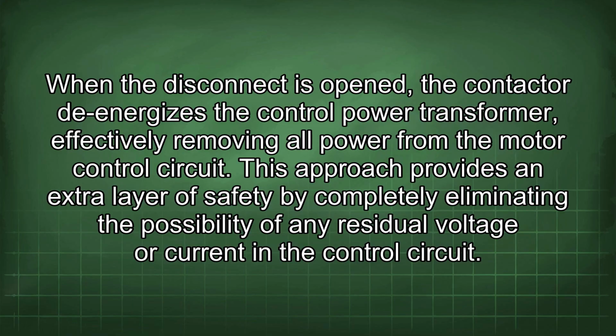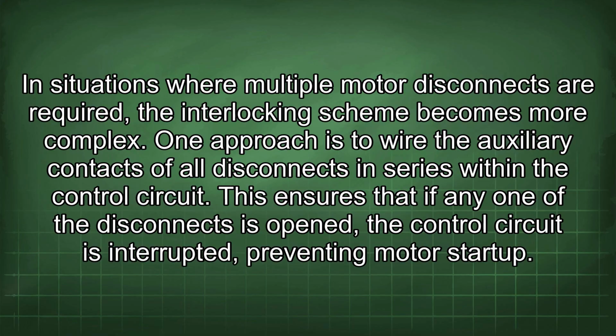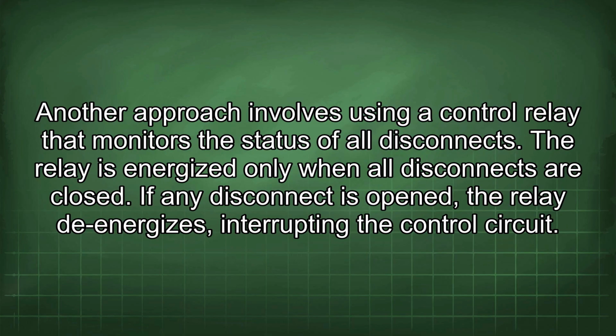In situations where multiple motor disconnects are required, the interlocking scheme becomes more complex. One approach is to wire the auxiliary contacts of all disconnects in series within the control circuit. This ensures that if any one of the disconnects is opened, the control circuit is interrupted, preventing motor startup. Another approach involves using a control relay that monitors the status of all disconnects. The relay is energized only when all disconnects are closed. If any disconnect is opened, the relay de-energizes, interrupting the control circuit.